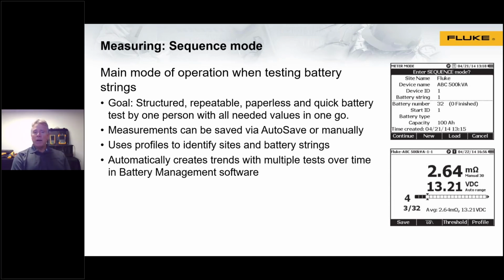You can set up user profiles, so locations, plant or area locations, or if you're in the business of battery testing, a service organization. It can be customer sites, areas in that site. You can have device names, battery strings with X number of batteries in the string. So you can create these profiles either in the tool, or you can create them in the software that's included with the tool. So we had said that trending is very important.